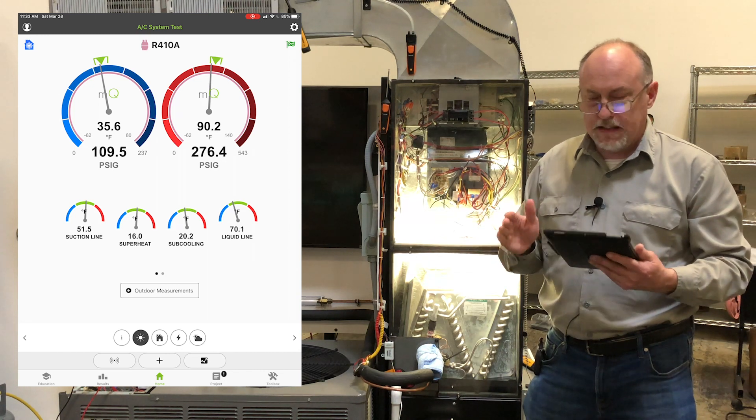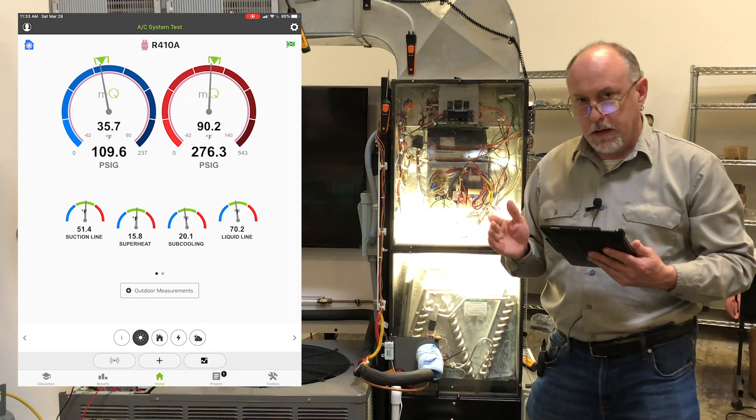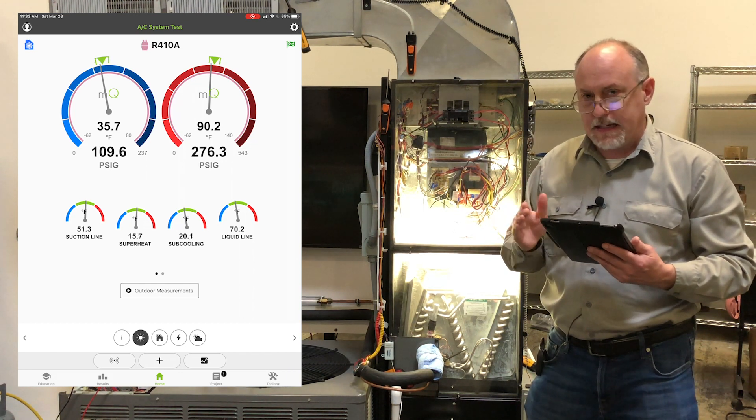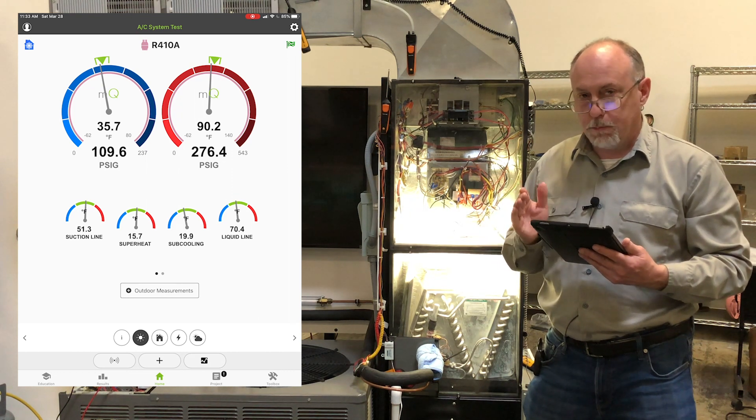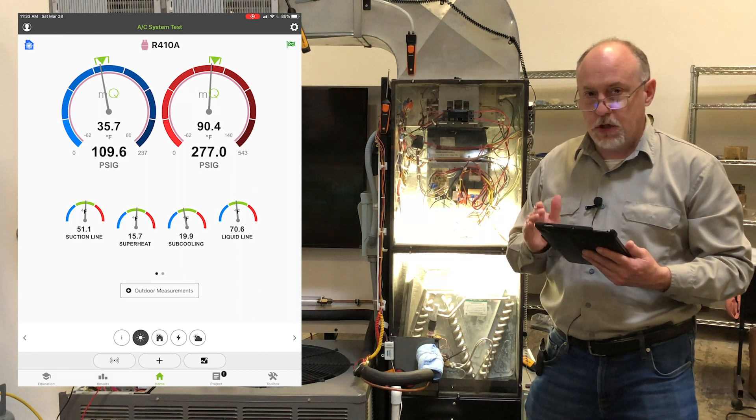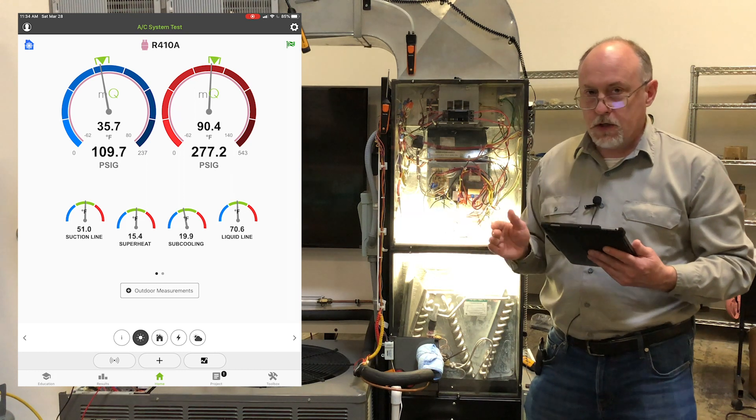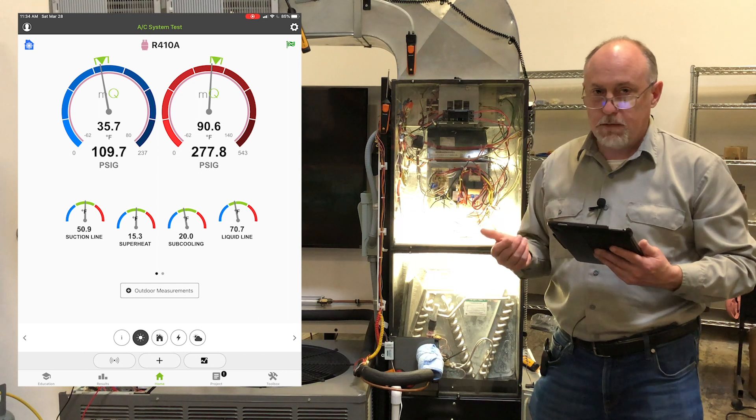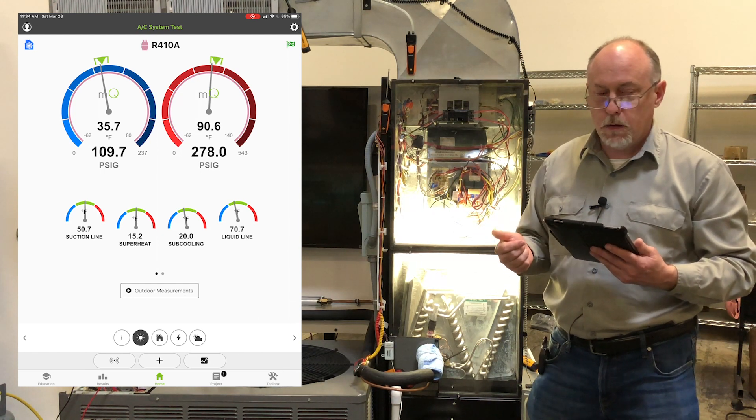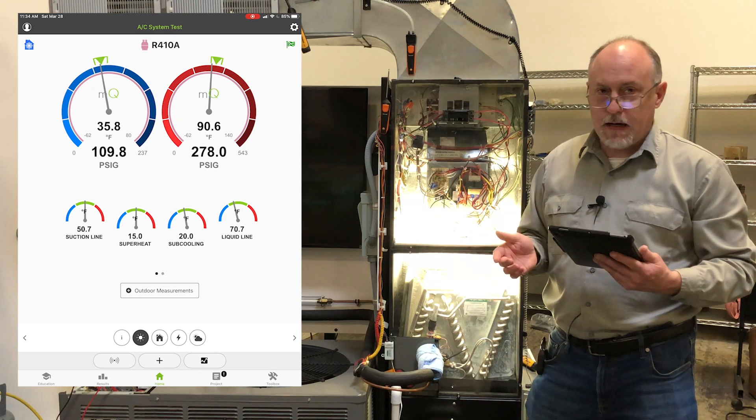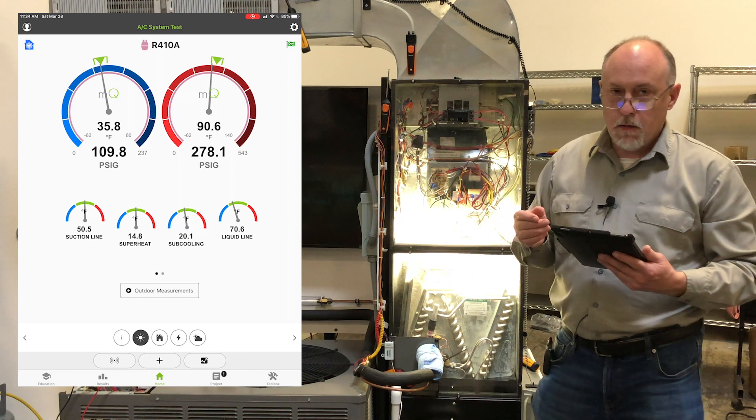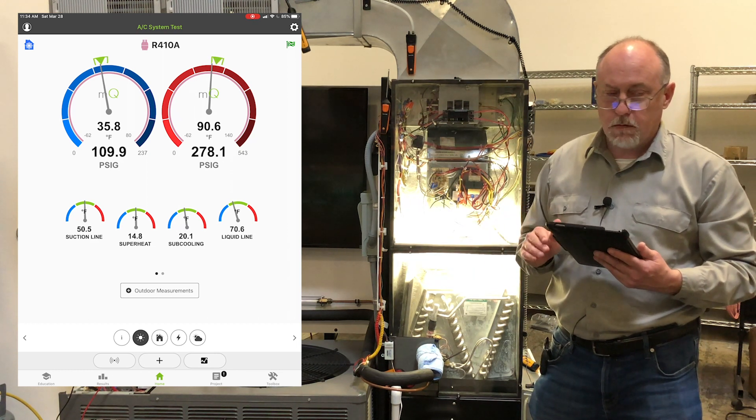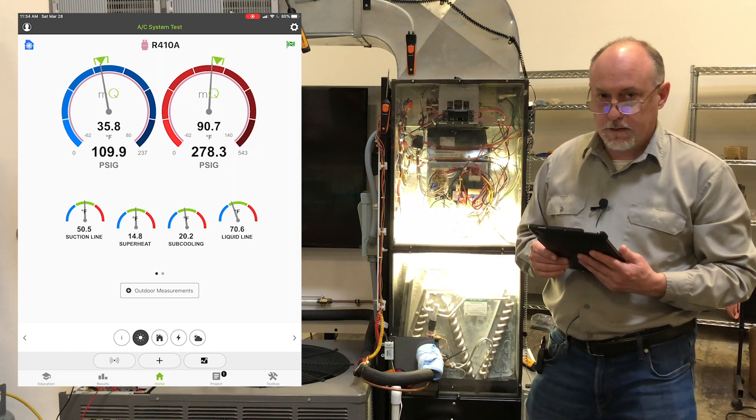So this is really the most powerful feature of MeasureQuick because it baselines your company. So everybody knows exactly how a piece of equipment is supposed to operate. And when we benchmark it going forward, we can be very assured that the diagnostics now are going to be much more accurate because we know exactly what the pressures, temperatures, superheat, subcooling, static pressure, and a host of other readings should be compared to the day they were installed. And it's something everybody should be using. Save that data in the cloud. Your data is your data, we don't sell your data or use your data. But this is probably one of my favorite features of MeasureQuick and something that you all need to be aware of and really should start to use. This is Jim with MeasureQuick. Thanks a lot for watching.